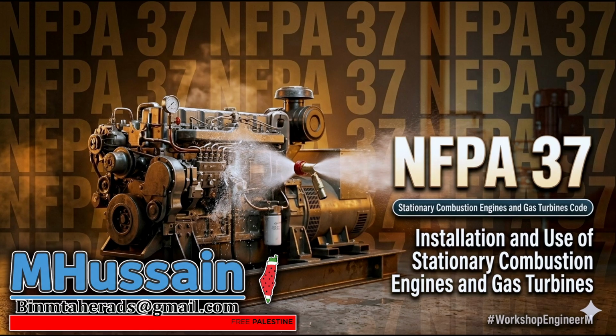No. The advice from experienced designers is to avoid exception 2 whenever humanly possible. Maintain a physical 5-foot separation. Because 5 feet is something you can measure with a tape measure. It ends the argument. Exactly. It changes a subjective debate into an objective fact. It keeps your permits from getting delayed.